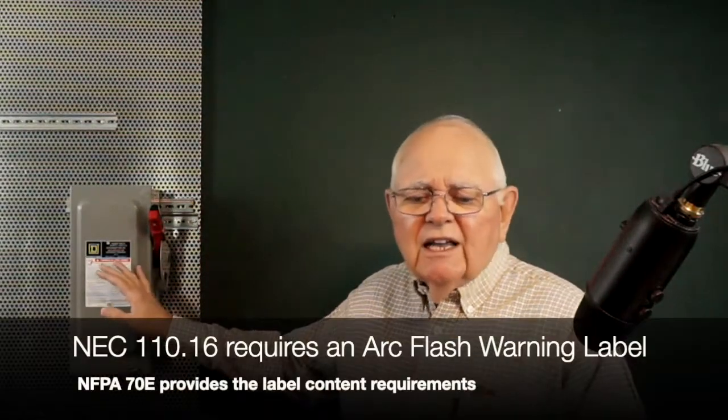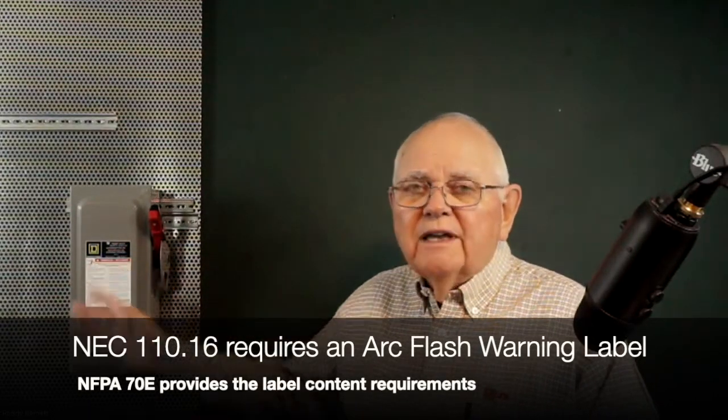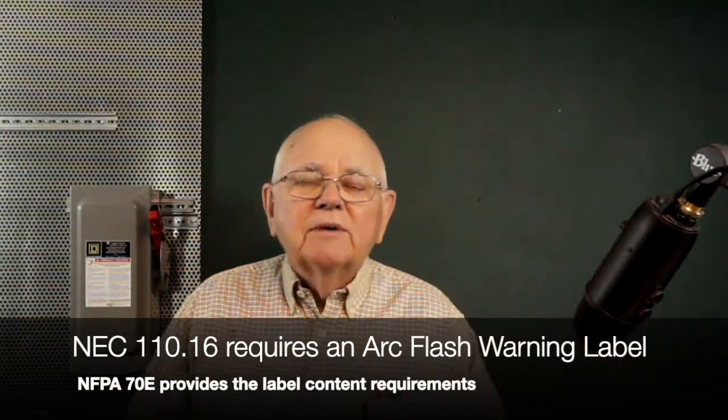I'm Randy Barnett. I'll be the facilitator for today. And today we're going to be talking about the PPE category method, the table method, the tables in 70E, electrical safety is what we're talking about. We know that according to NEC 110.16, if I'm going to go up and operate a piece of equipment like this disconnect switch, there needs to be a label on there to warn me of any arc flash hazard that might be present.